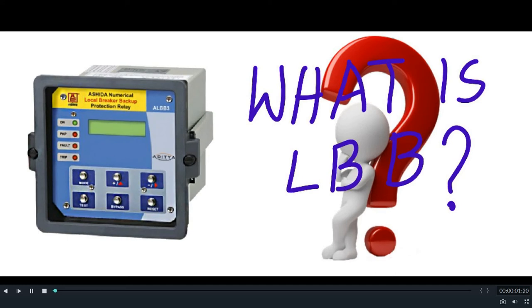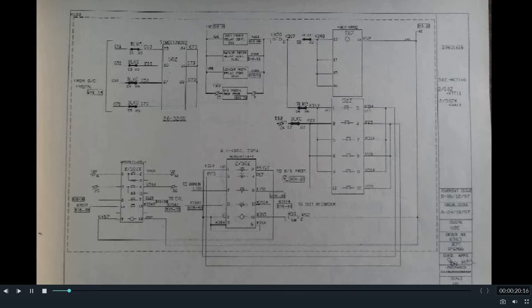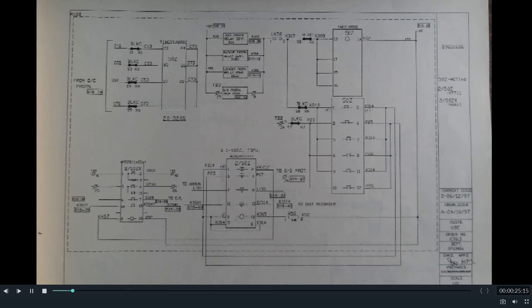Hello friends, welcome to my YouTube channel Technical Experience. Today I shall be discussing what is LBB, or what is Local Breaker Backup, used in a substation. Local Breaker Backup is a technical condition which comes into force when a circuit breaker comes into a contingent condition. During a fault, when a particular circuit breaker fails to operate, the other associated circuit breakers that come into action to rescue the situation — that kind of arrangement is called LBB or Local Breaker Backup.